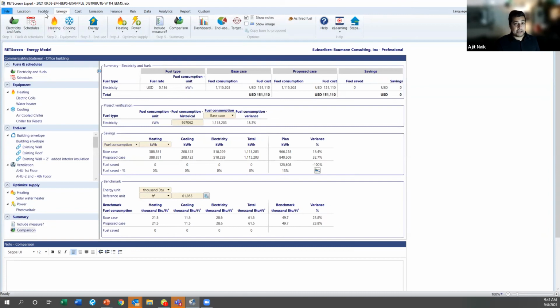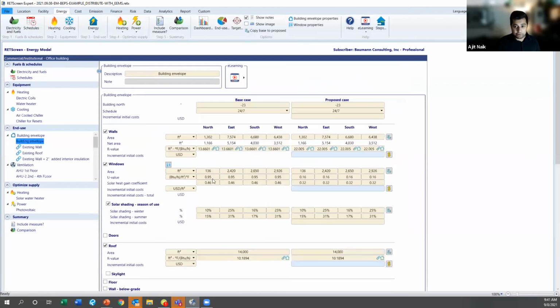So we went back on site, took a deep dive into what went on, and we actually realized that there was a partial glazing upgrade. We had assumed that the windows were all single pane everywhere and they were really old and bad, but they were actually quite a bit better performing than we assumed. We found a cut sheet for what these values were, and modeled the U value of those windows appropriately. So before, where we assumed they were very high and poorly performing windows, we hadn't accounted for that window upgrade, which improved that window performance.